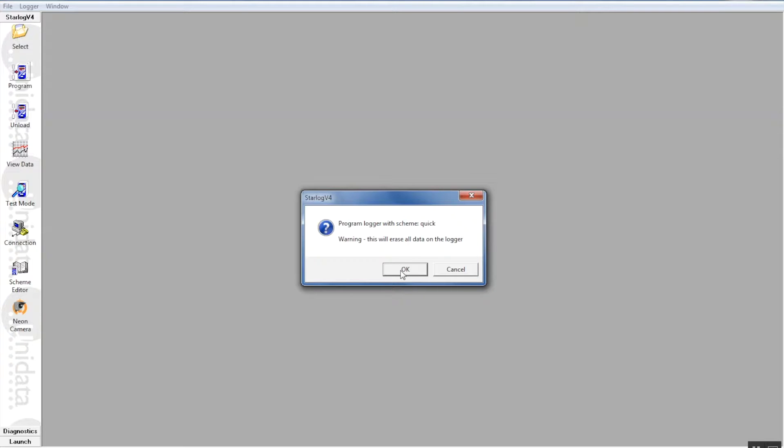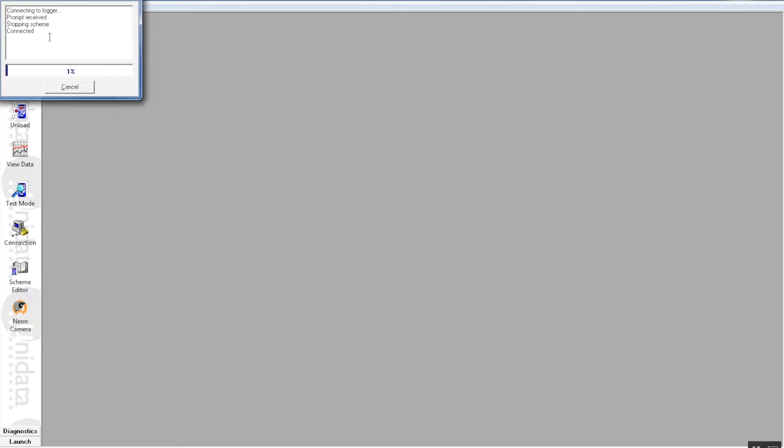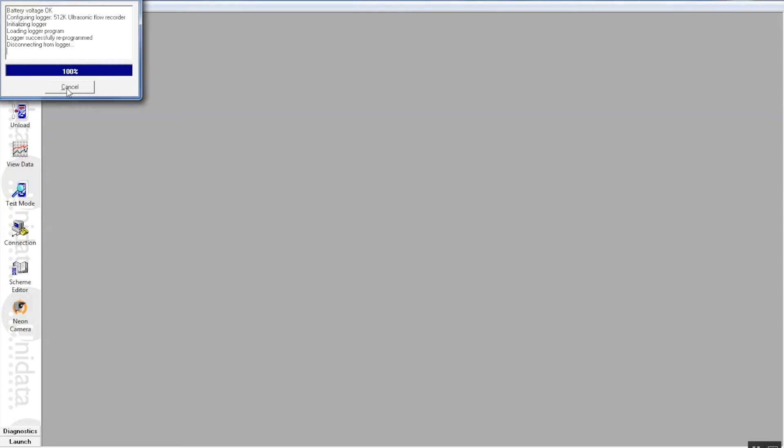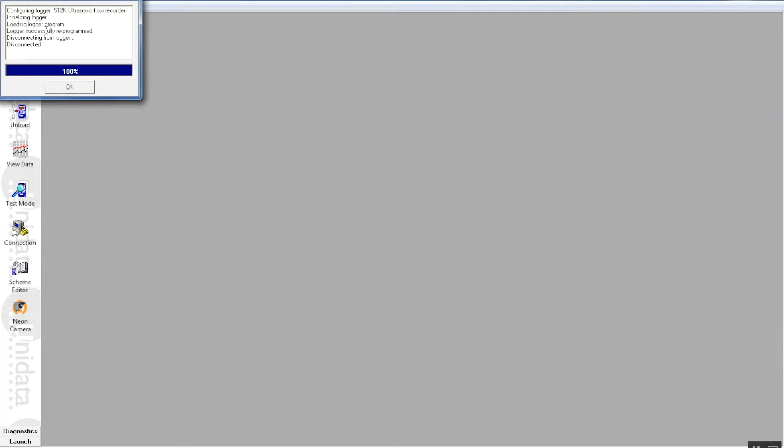We don't worry about what's on the starflow at the moment, we can press OK on this dialogue and we can see here it opens another smaller window which has a progress bar indicating the progress of the scheme upload. It's a very good idea to keep an eye on this screen when it's uploading. You must always see Logger successfully reprogrammed. You can see that clearly here and that means the starflow instrument has been programmed successfully.